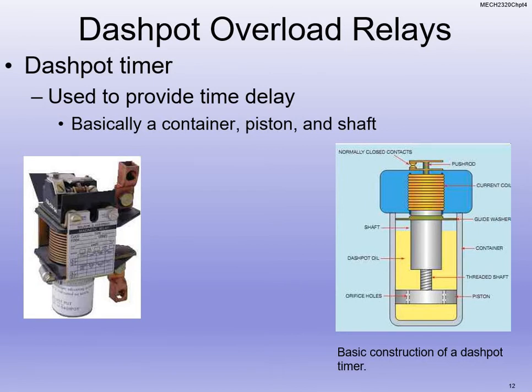Because, like I said earlier, when we had the other type of heat fuse, sometimes we want a large inrush current to get the motor going, but we don't want it to operate at that. It's just an inrush. So we put a Dashpot timer on there. So it's a time delay.